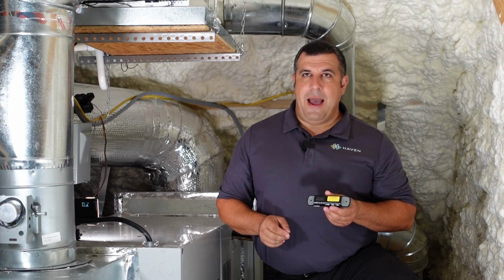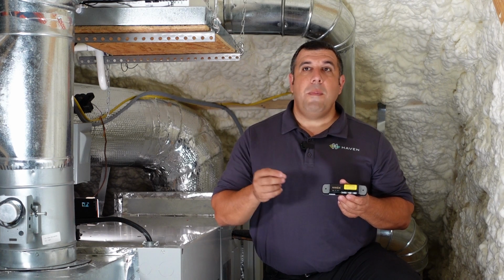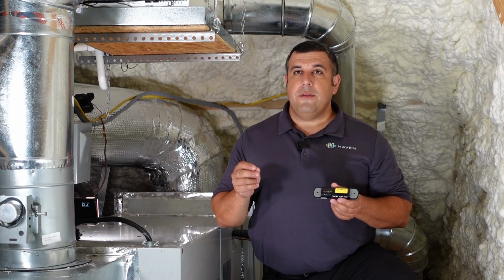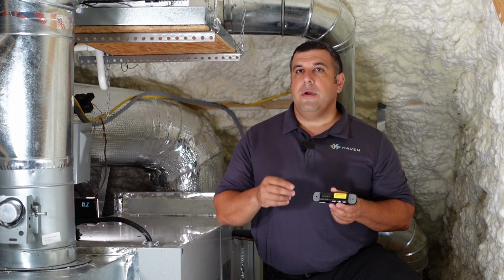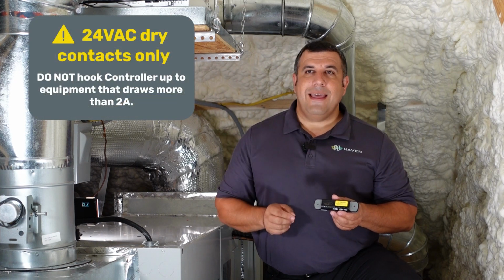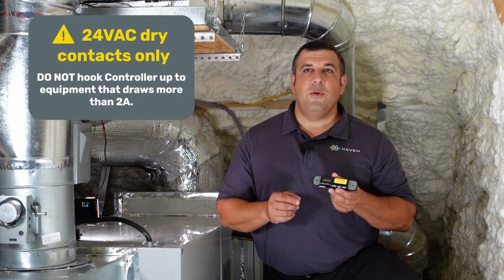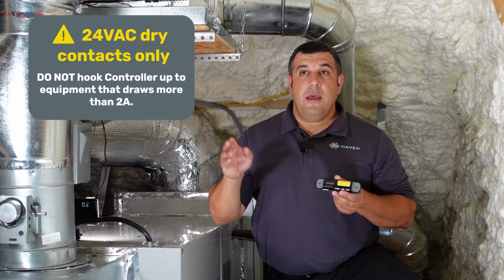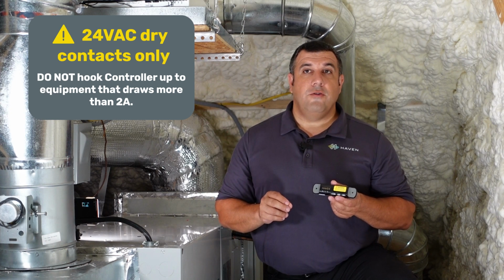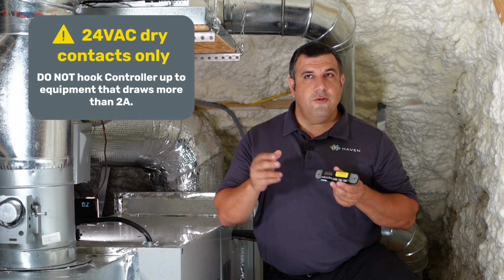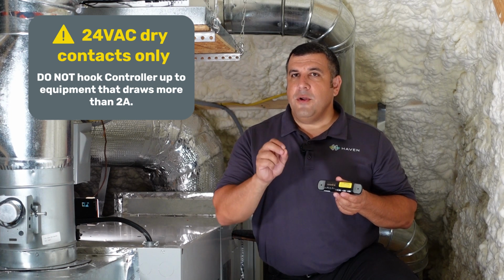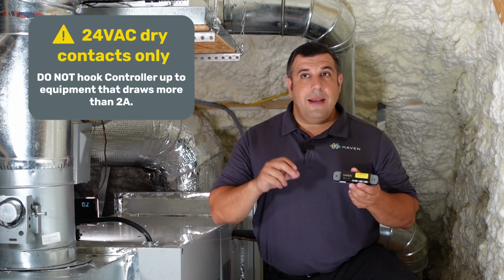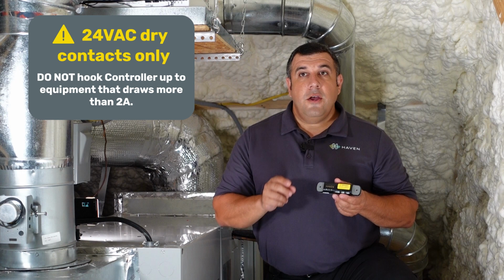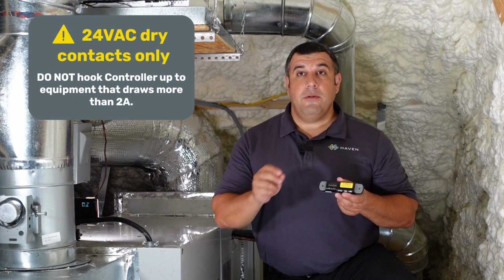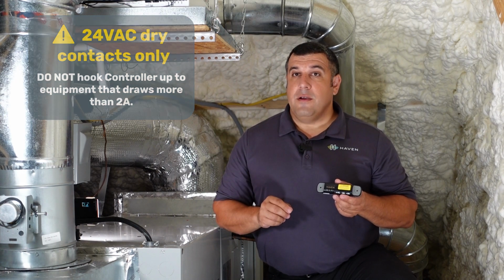Now let's talk about power. The controller is a low-powered product using only 10 watts during startup and a few watts during operation. Please note that the Haven controller is only designed to switch loads under 30 volts with 2 amps max current draw. Do not attempt to use the dry contact outputs to switch 120 volt loads or anything drawing more than 2 amps. Doing so could cause damage to both the controller and the HVAC equipment.